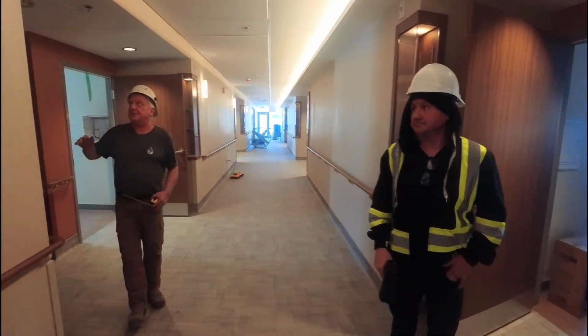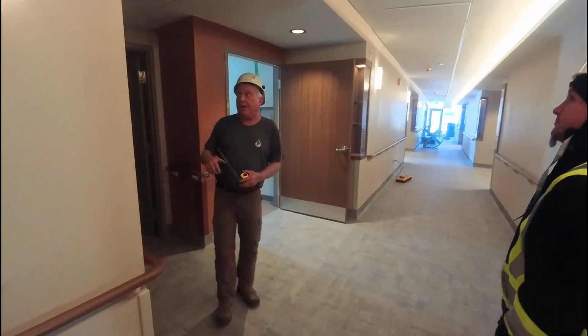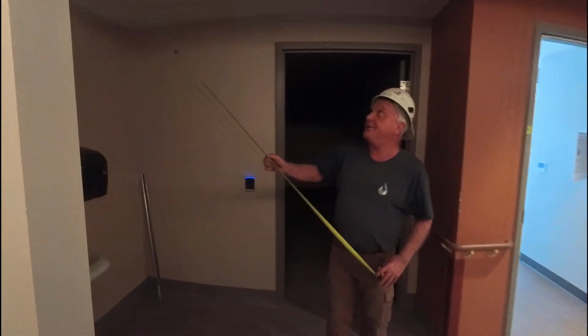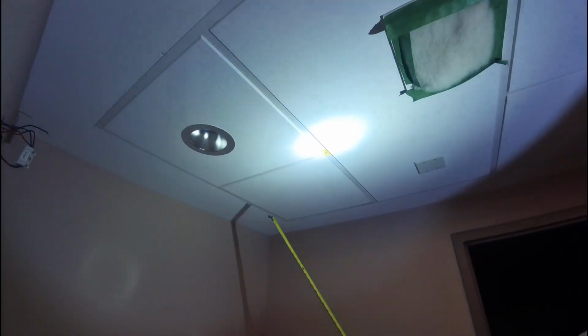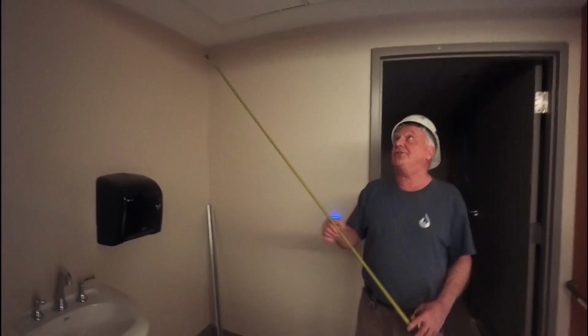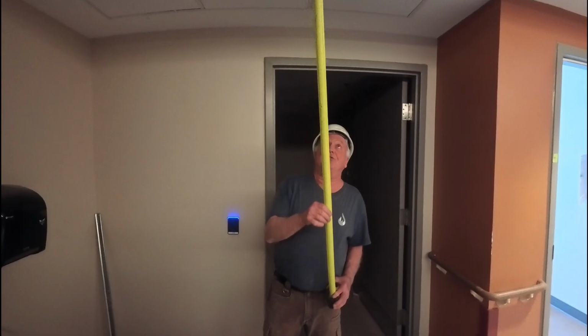There's the access door there. That's an access door for the fire damper, just to look. An inspection port is what we call that. And on this side is the return fire damper coming into the wing. And again, you'll see the fire smoke damper symbol. This tile can be removed, and up above you'll have all the hardware that's required for the fire damper. That's the electrical tie-ins and sensors and cleanouts, etc.